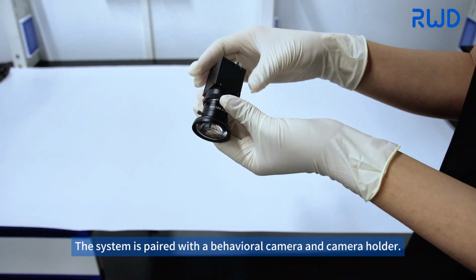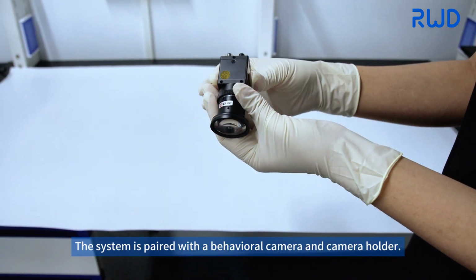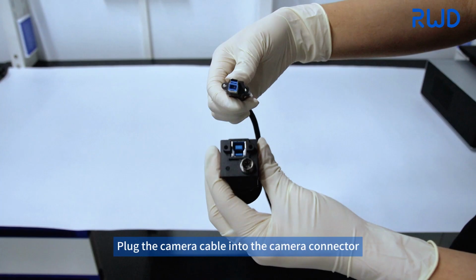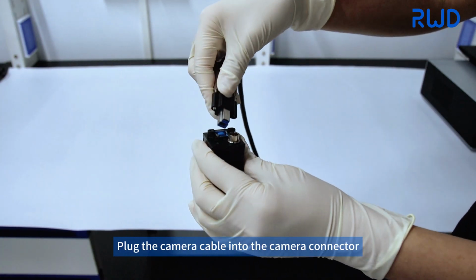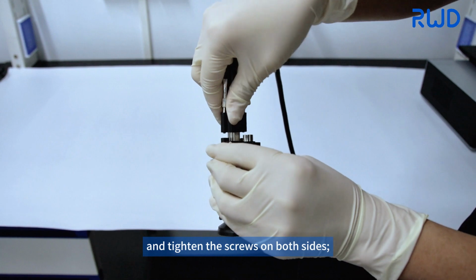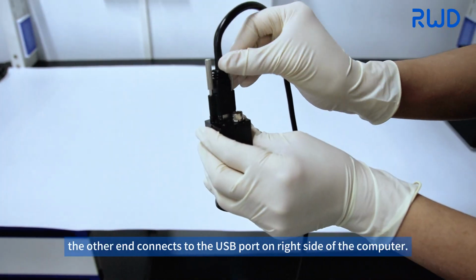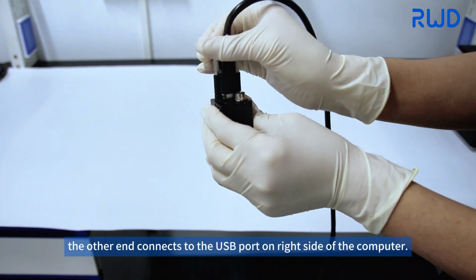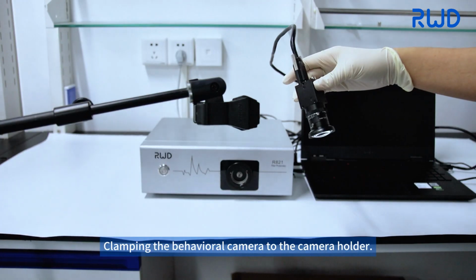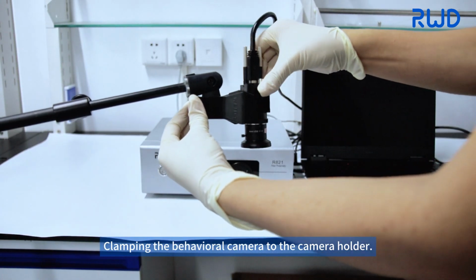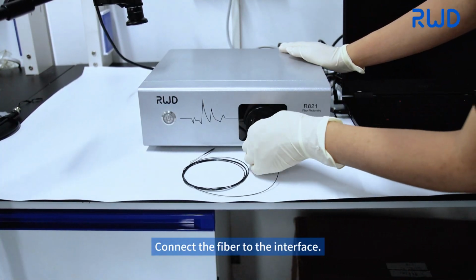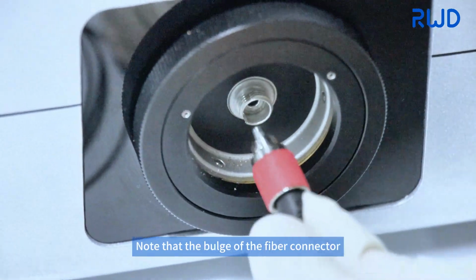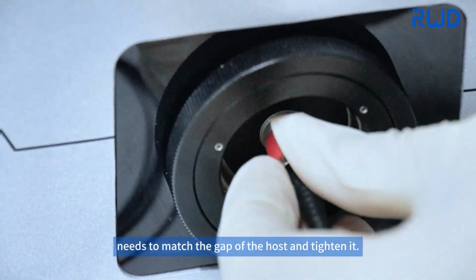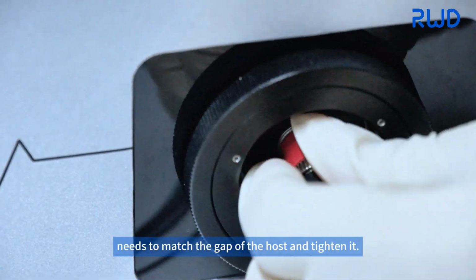The system is paired with a behavioral camera and camera holder. Plug the camera cable into the camera connector and tighten the screws on both sides. The other end connects to the USB port on the right side of the computer. Clamping the behavioral camera to the camera holder, connect the fiber to the interface. Note that the bulge of the fiber connector needs to match the gap of the host and tighten it.